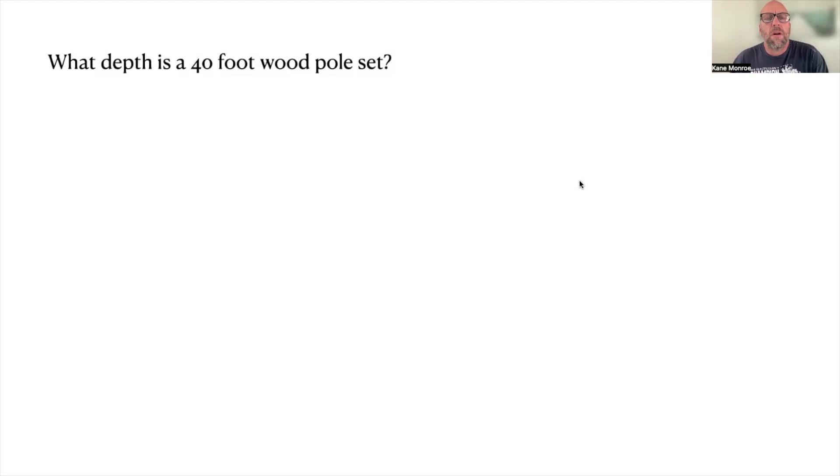Oh this is a good one. What is the depth of a 40 foot wooden pole? What depth is a 40 foot wooden pole set? That is in a lineman's book and what it is, it's six feet. So it's 10% of the pole, 10% of the pole plus two feet. So you got to remember that, 10% of the pole would be four plus two would be six.